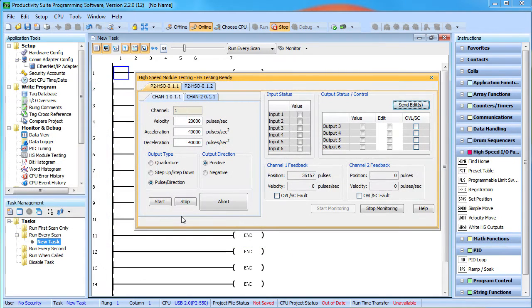So if the motor does move as expected, we know our issue is back in the software. If the motor doesn't move, the issue is in the hardware. This tool just cut the scope of our debug problem in half and tells us exactly where to focus our attention — hardware or software. And since we have complete control over the pulses generated, we can also use it to verify that we have the stepper drive configured correctly.